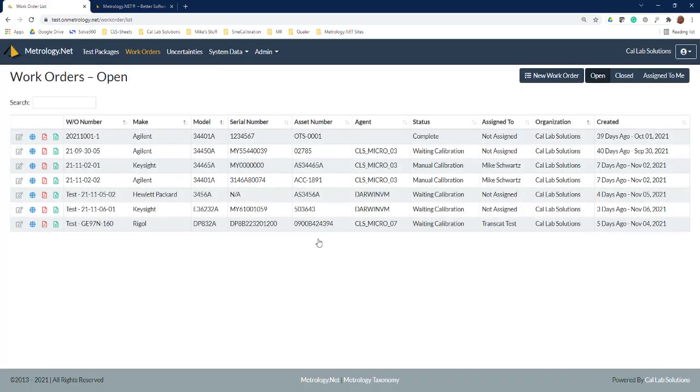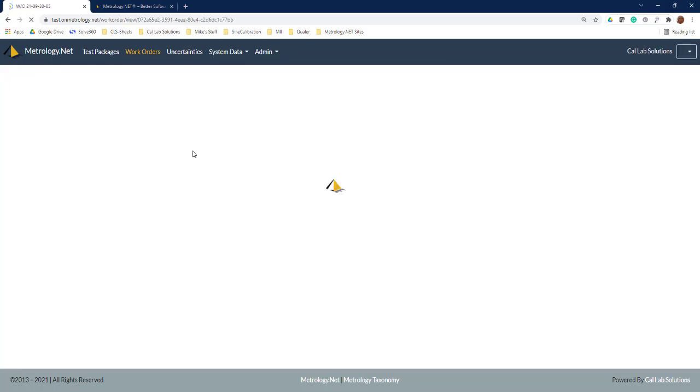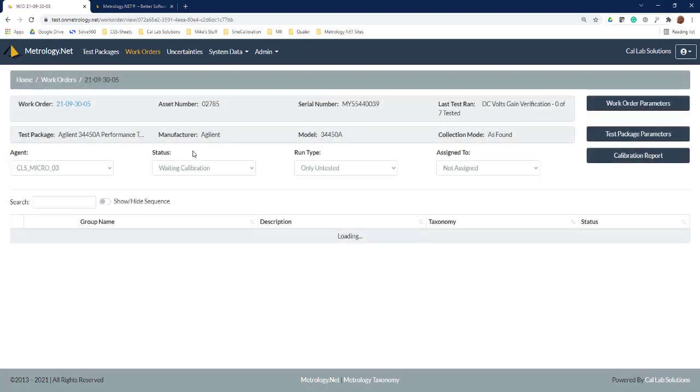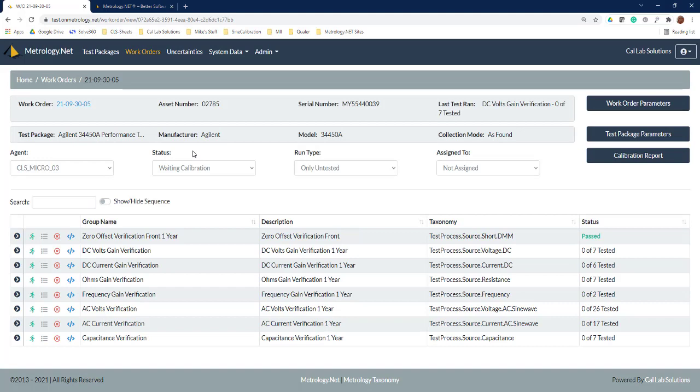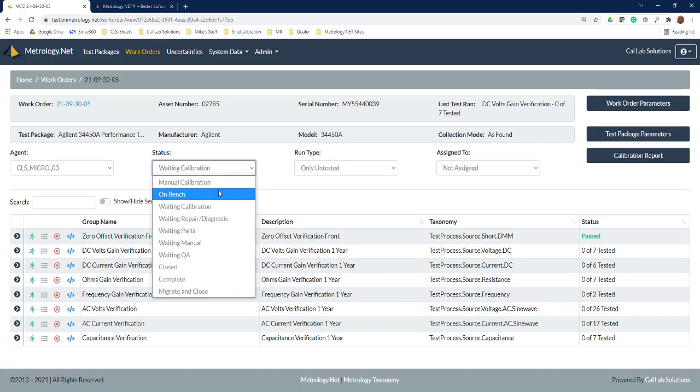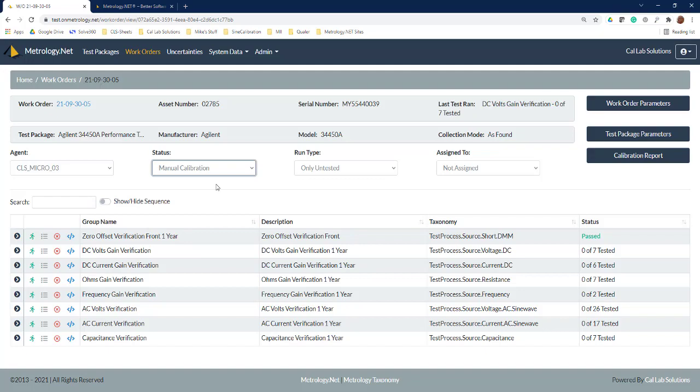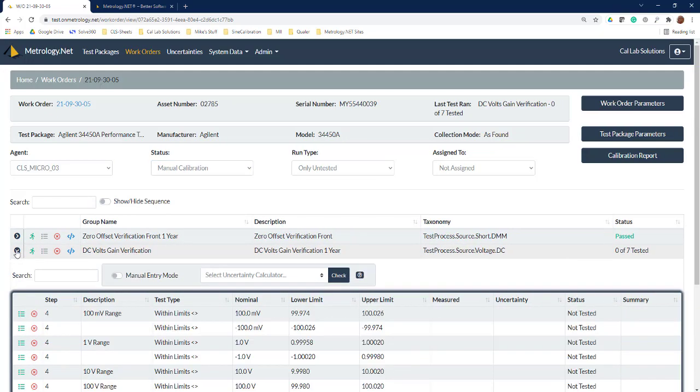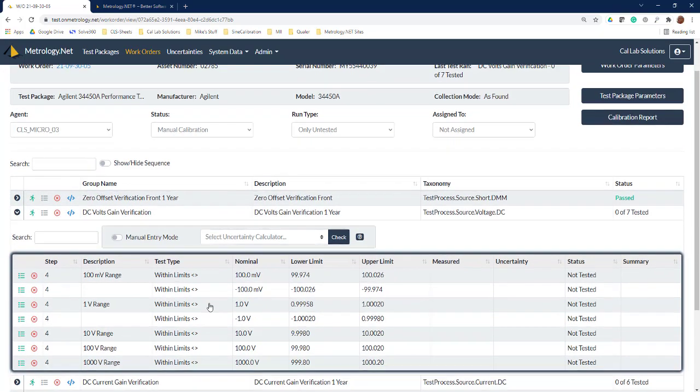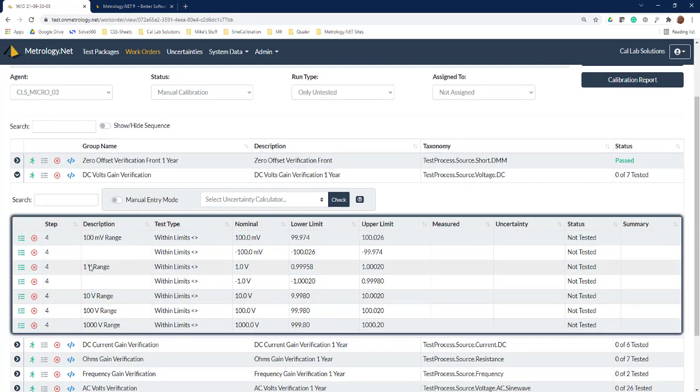Let's start off by logging into metrology.net. As we log in, it's going to move us into our work order page and we'll grab the 34450 that we're working on. The first thing we're going to want to do is change it to a manual calibration, and then once we've changed it into a manual calibration we can expand out DC voltage or any one of the test groups.